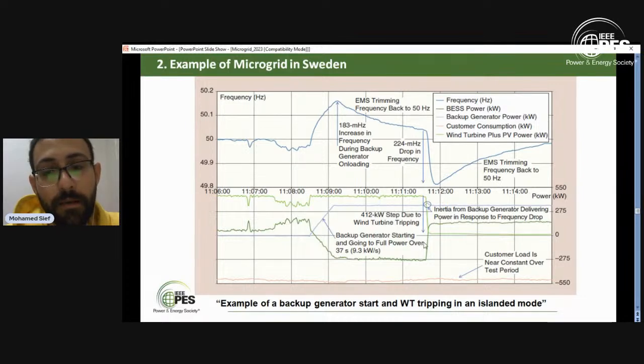At this moment, as you see, a small notch came from the inertia of the system because we have a sudden drop in frequency. So the diesel generator, as a rotating machine connected to the grid, reacts like action and reaction. The action was losing the rotating machine, causing the frequency drop, so the diesel generator reacts by slightly increasing power generation to compensate for this loss of frequency.